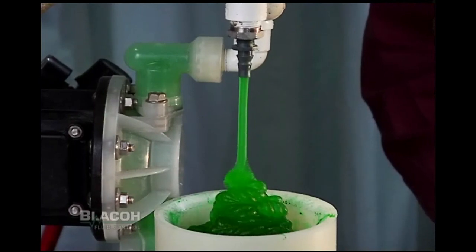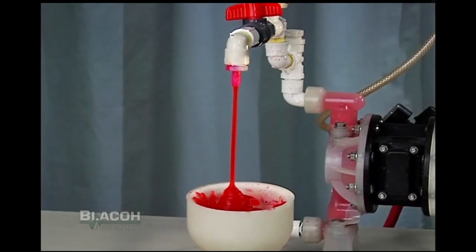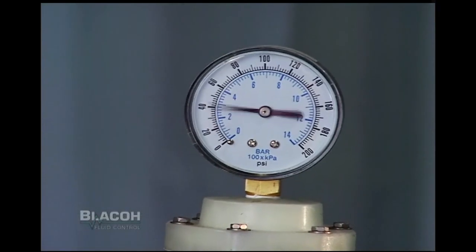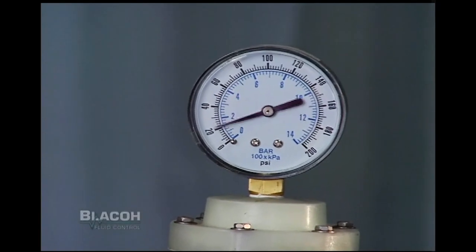One side is pumping with the benefit of a pulsation dampener, the other without. The side without the pulsation dampener creates a pulsating flow, and that flow can be observed on the gauge as a rise and fall of pressure fluctuating with each stroke of the pump.